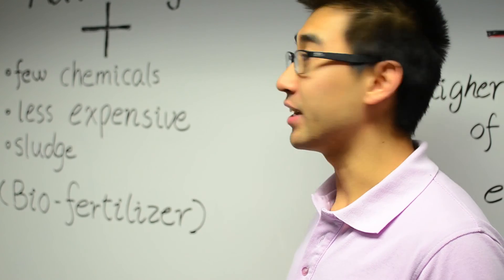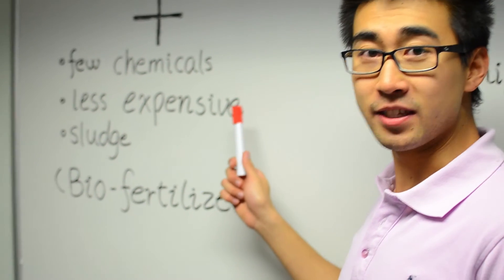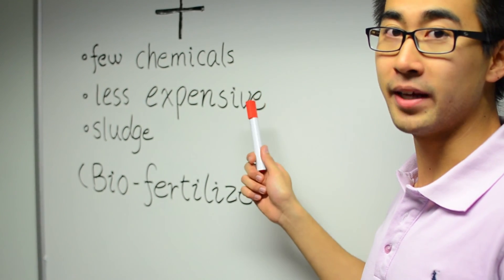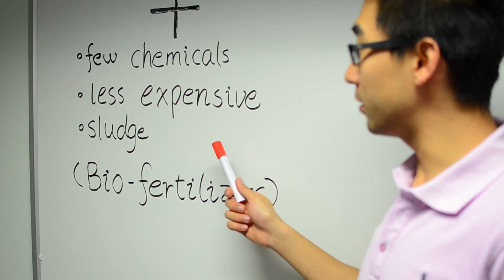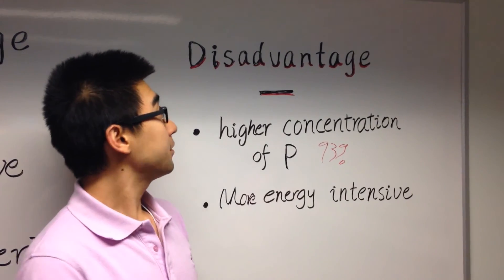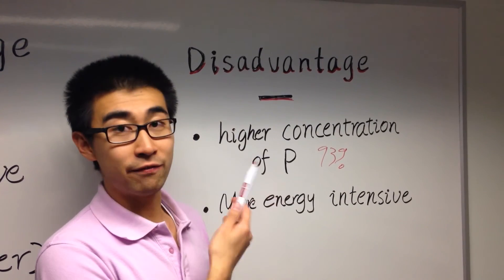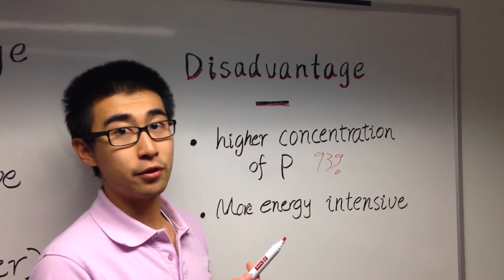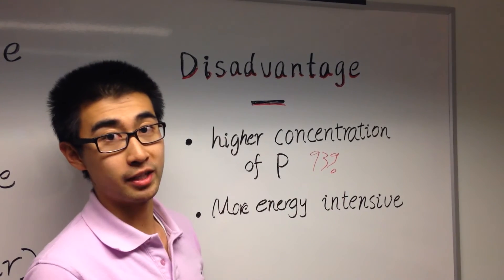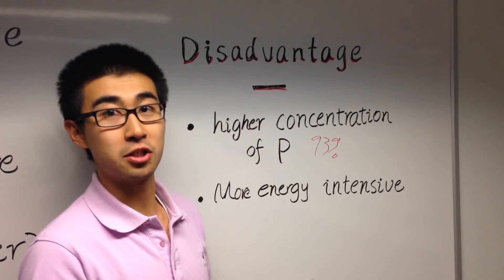When it comes to phosphorus removal, EBPR has a few advantages and disadvantages when compared to the chemical method. On the advantage side, EBPR requires fewer chemicals as it's a purely biological process, and as a result, it's less expensive because there aren't chemicals to replenish continuously. Further, the sludge can be used as a biofertilizer which can be reapplied to the fields because there are no chemicals involved. On the disadvantage side, the concentration of phosphorus removed tends to be lower, although modern methods still accomplish a 92% removal rate. Also, it is more energy intensive as the aerobic part of the process requires constant oxygen sparging.